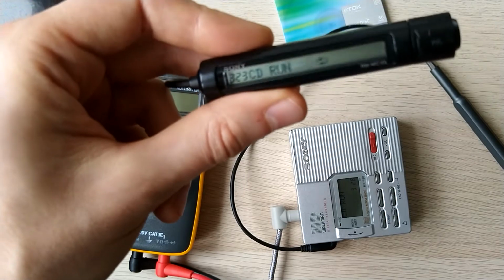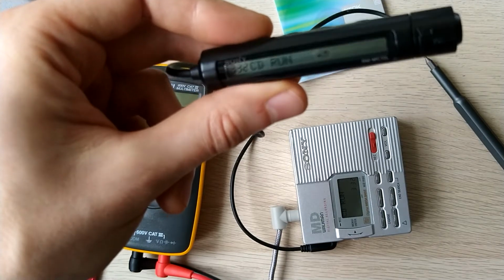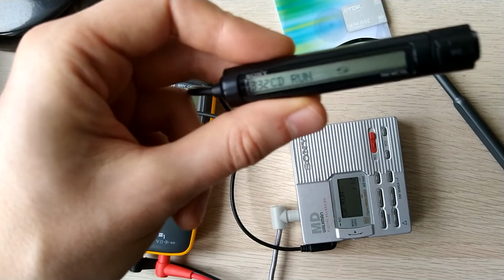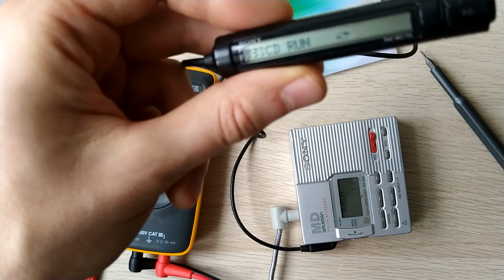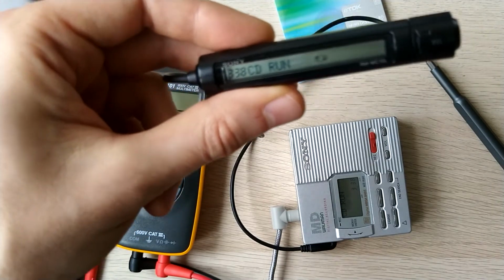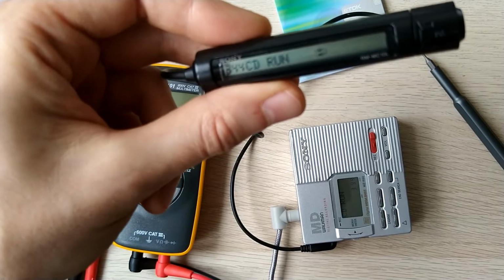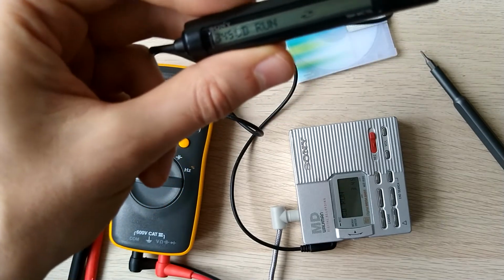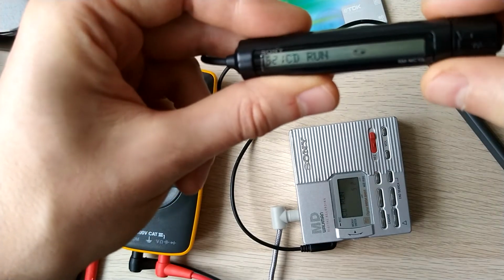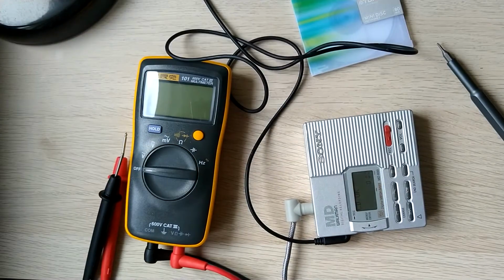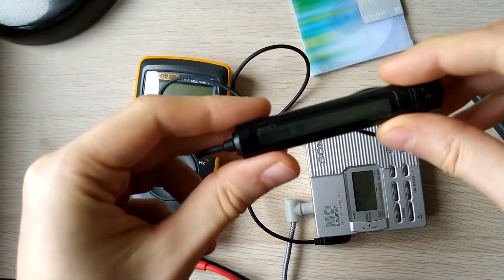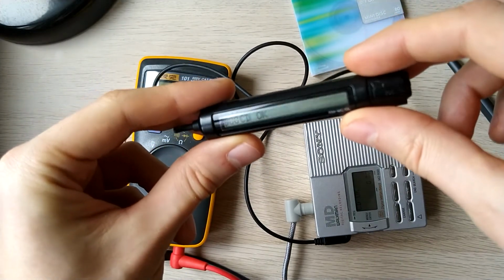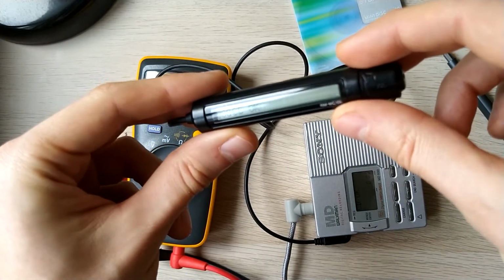This process may take a couple minutes. It depends on the device. For some devices it's very quick, almost instantaneous. On this particular device it takes a while, so I'm going to cut here and come back when this auto-calibration process is finished. Okay, we are back. So the first half of the auto-adjustment routine has completed. The display shows CD OK.